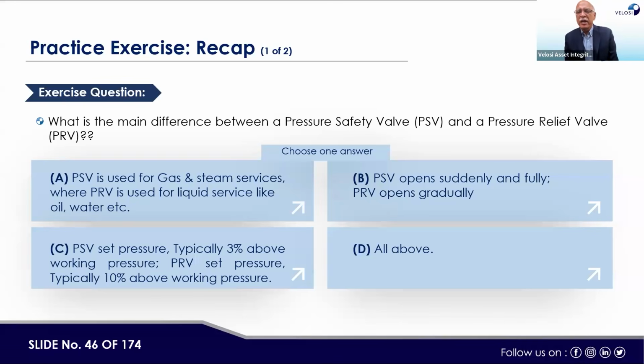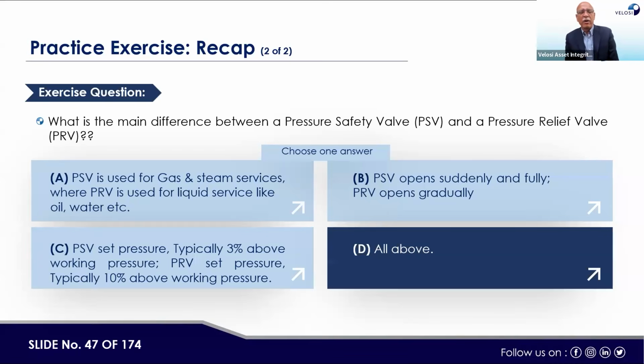PSV opens suddenly and fully, PRV opens gradually. This could be right also. PSV set pressure typically 3% above working pressure. PRV set pressure typically 10% above working pressure. All of the above. So what is the answer? To me, yeah, many answers are right. Yes, the answer is D, all of the above.